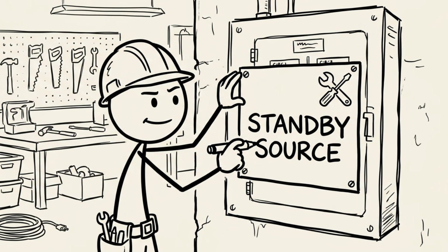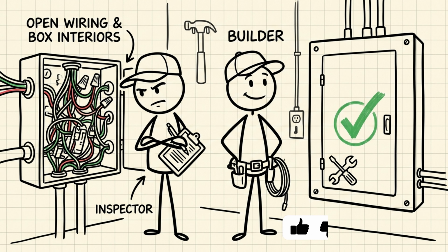Phase 5. Install every required sign, the permanent placard at the main service equipment, identifying the standby source and its location, and a second one at any remote grounding point. Phase 6. Rough-in inspection, with every wire and box interior fully visible before anything is covered, followed by final inspection once the system is complete and the breaker directory is filled out. Only after a passing final inspection is this system legally and safely live.